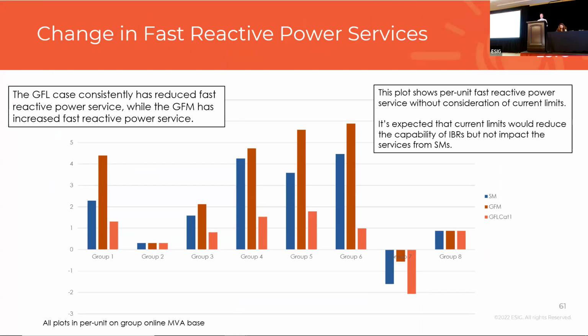What we see here, again, starting in blue with the synchronous machine cases, is significant levels of service in group 5 and 6, the synchronous machine dominant groups. But we now also see a lot more of these services coming from the grid forming dominant IBR case, and less of these services from the grid following. Again, consistent with what we'd expect, consistent with what we've seen at the individual resource level.